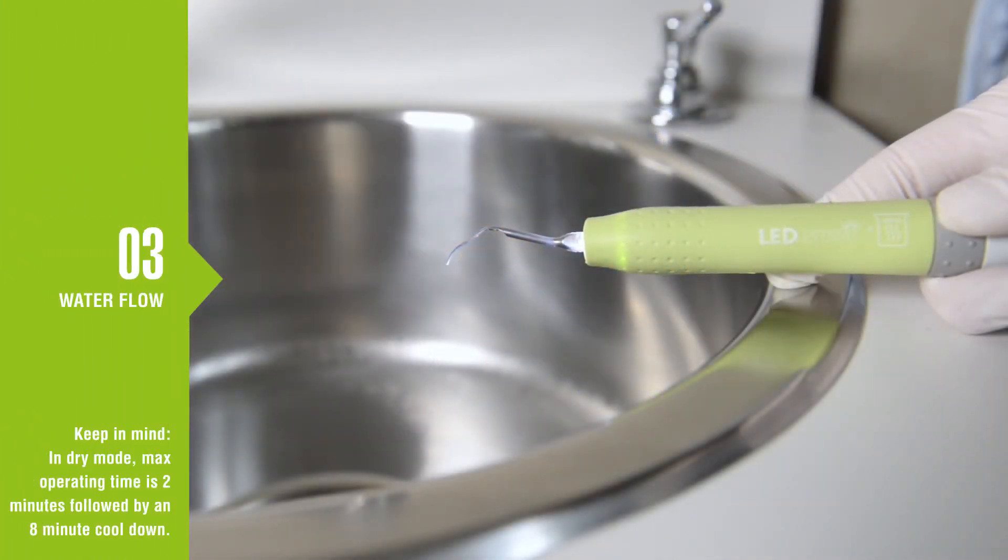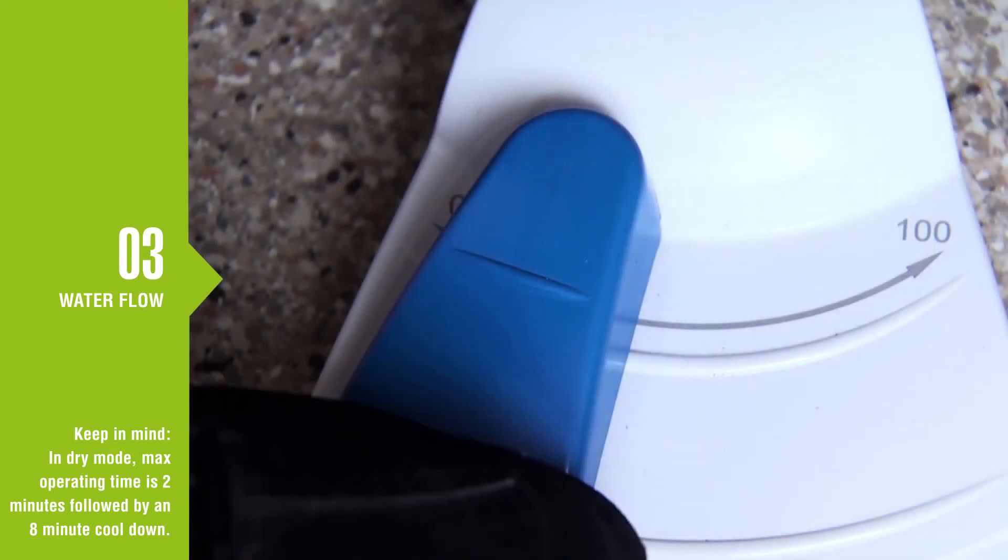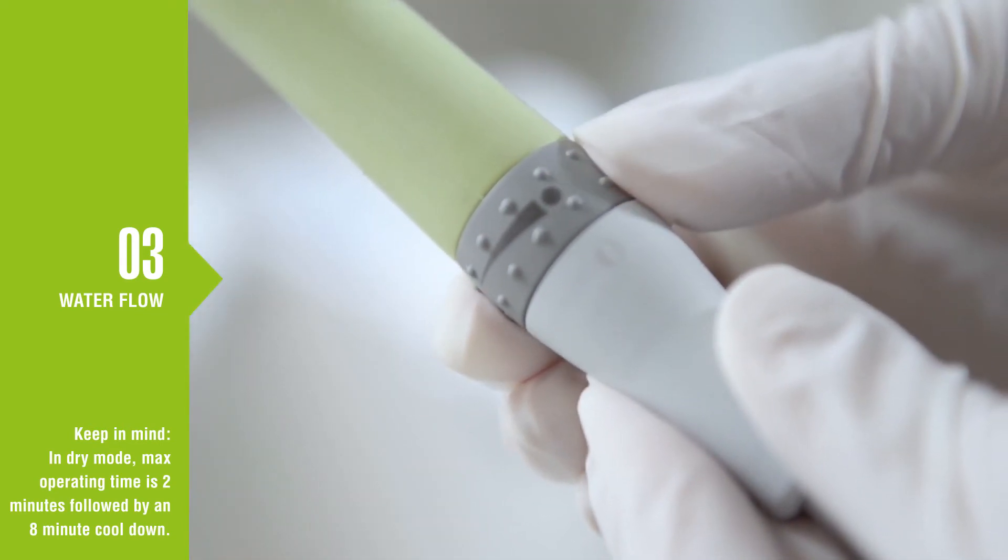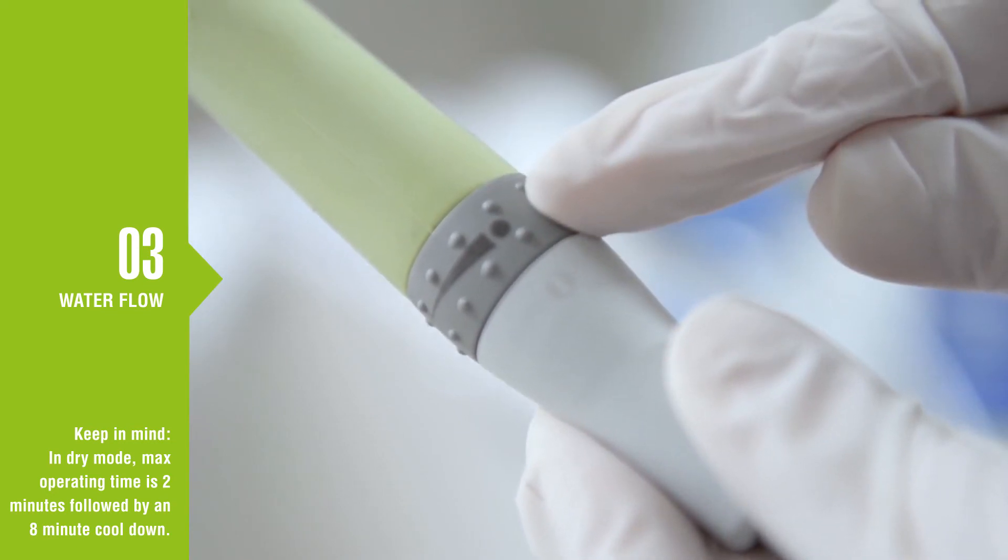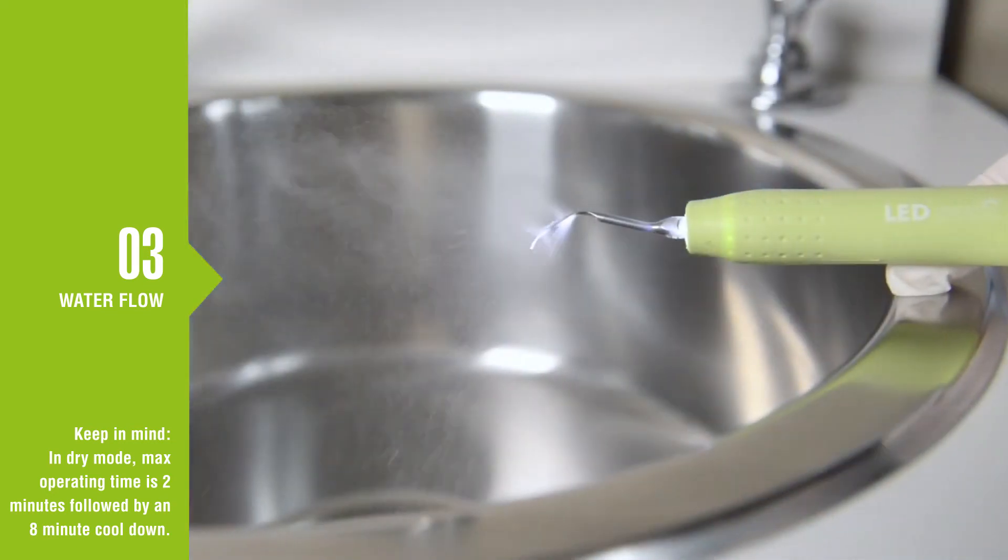With the scaler handpiece over the sink, press the foot control pedal and adjust the water flow using the valve on the handpiece. The dot on the connector indicates max water flow.